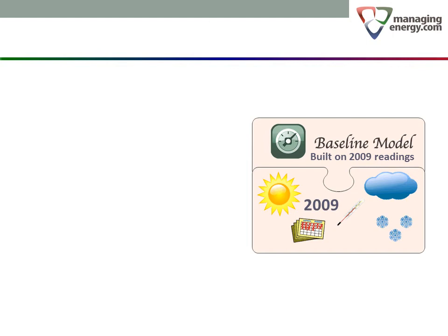But what if 2009 was much warmer than usual? You would then be adding a bias toward less heating and more cooling to all later calculations. This effect is a particular concern if you want to forecast future energy consumption.